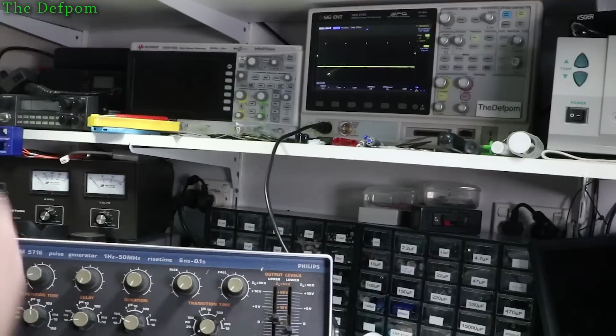Now I figured out what was going on before when I was trying to get these four controls here to work, and they weren't doing anything on the pulse output, but they were working on the auxiliary output. The reason is this is set to square wave, right? Because it's square wave, these controls are disabled. It passes that signal through to the amplifier board and it does a square wave. So I need to set it on pulse. Now we've got pulses, and now I can actually control delays and durations.